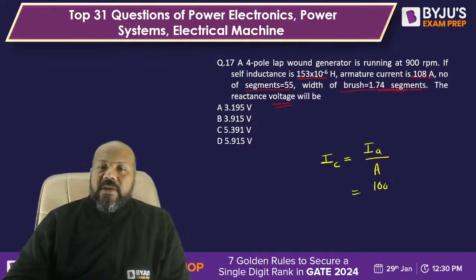IC is the current in the parallel path, so the total armature current divided by the number of parallel paths gives the current in each parallel path. Total armature current is 108 amperes, divided by the number of parallel paths. Since it is a lap-wound machine, number of parallel paths equals number of poles, that is 4. So 108 divided by 4 equals 27 amperes, which is the current in each parallel path.